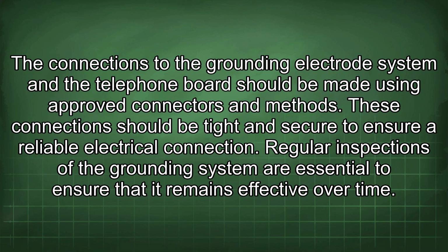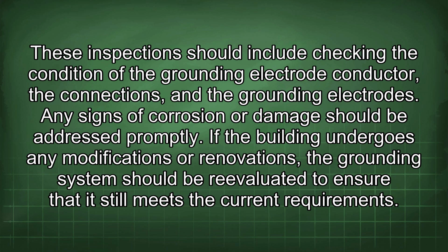Regular inspections of the grounding system are essential to ensure that it remains effective over time. These inspections should include checking the condition of the grounding electrode conductor, the connections, and the grounding electrodes. Any signs of corrosion or damage should be addressed promptly.